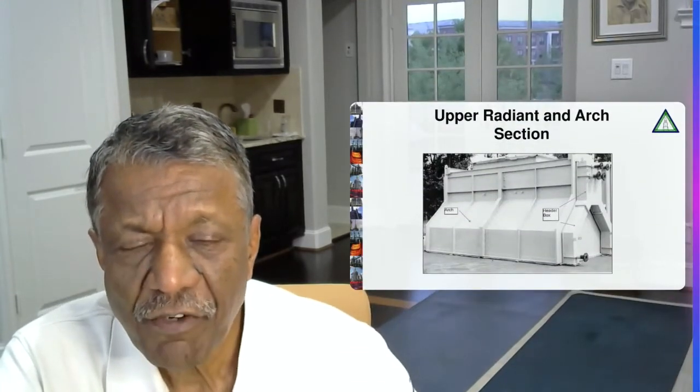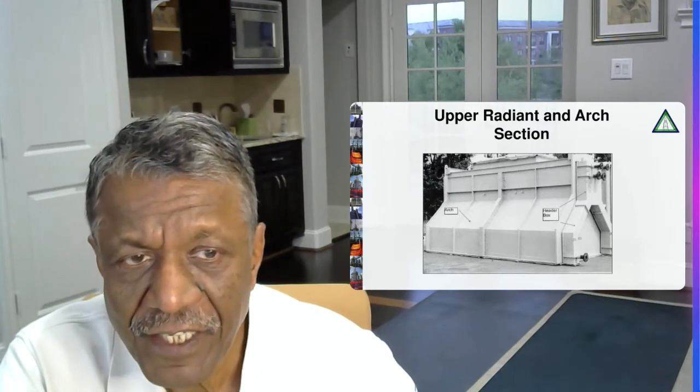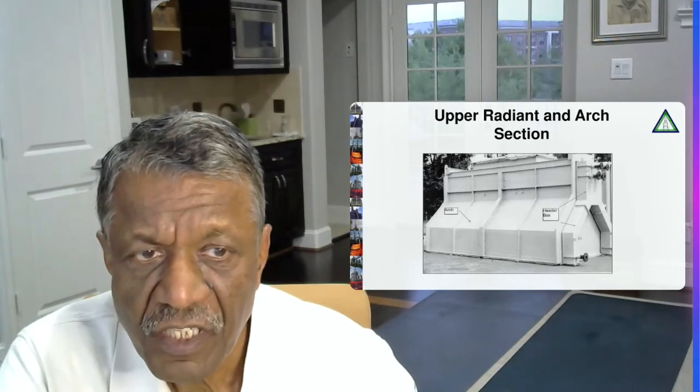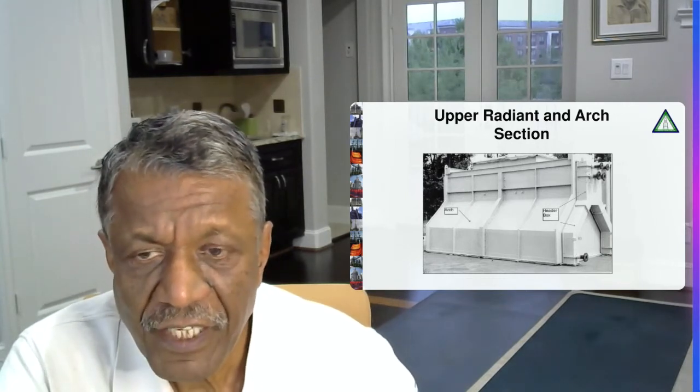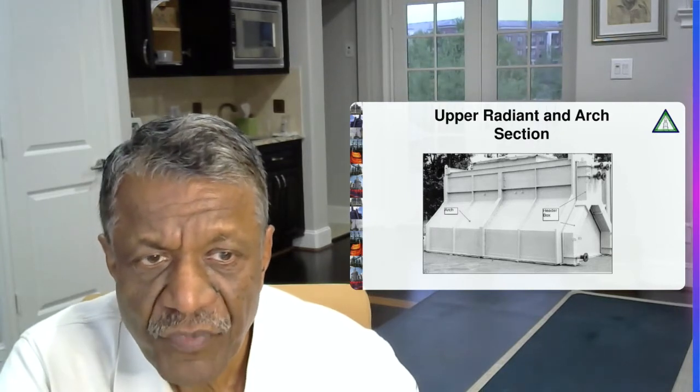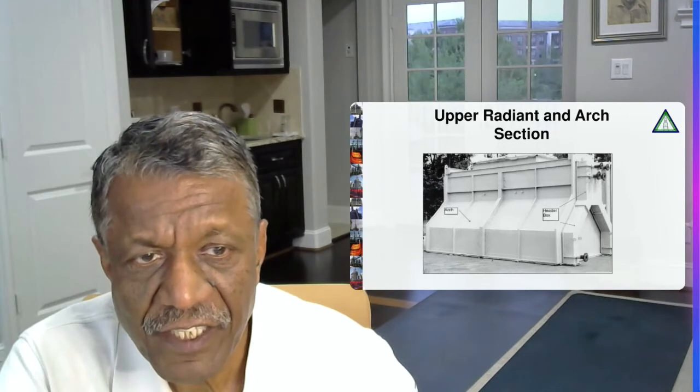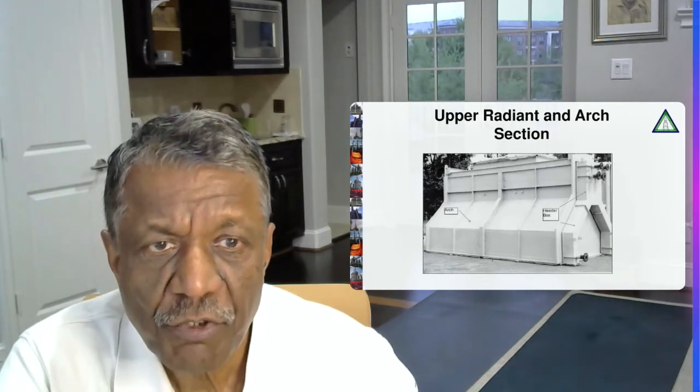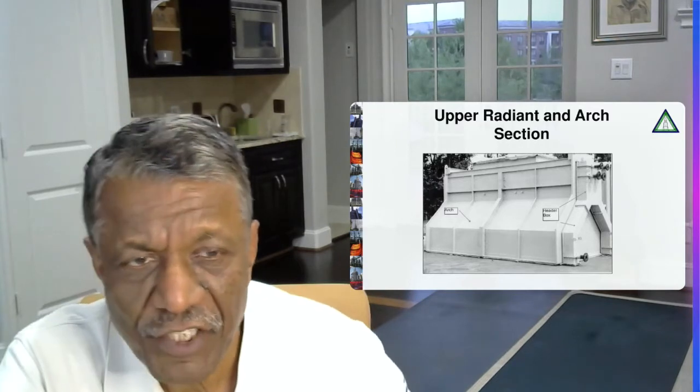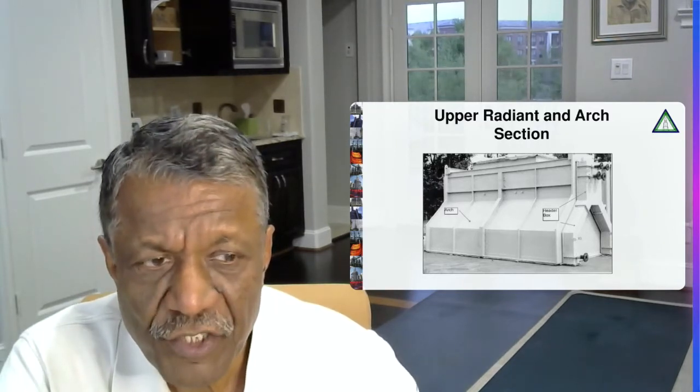The second type of heater we normally see in the industry is a cabin heater. And here is a picture of an upper radiant section and arch section. And you can see the header boxes. In a cabin heater, the tubes are laid out horizontally and we have header boxes sometimes on both the sides which are containing the return bends. You can also see, this is a very small heater, so you can see a convection section in this picture as well.